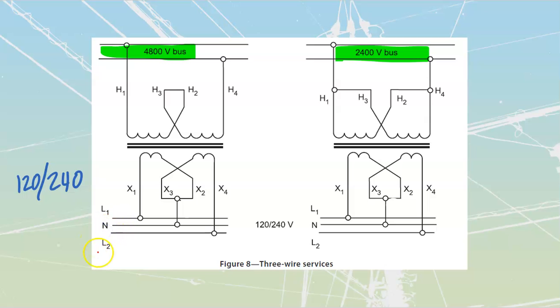If you connect a device across from line to neutral, say right here and here, current could run through my transformer and back out to that device. So we can get a 120 volt device connected from line to neutral. I could also connect another 120 volt device across from here to here, supplied from line over to neutral as well. So we see we can get our 120 volt systems, and we should also be comfortable that we could get a 240 volt system supplied from line over to line like that. This is our standard three-wire transformer connection.